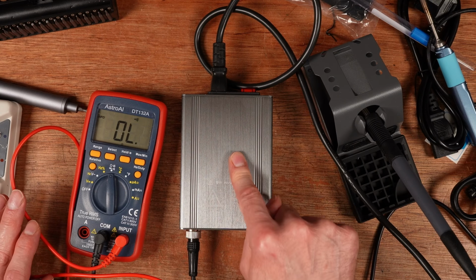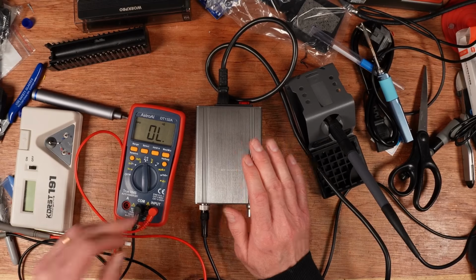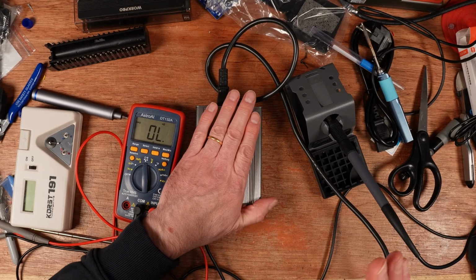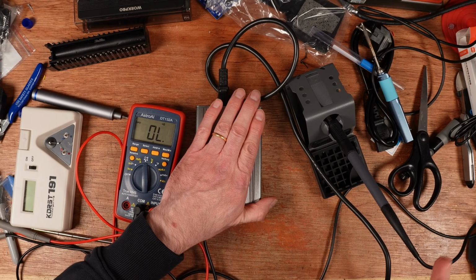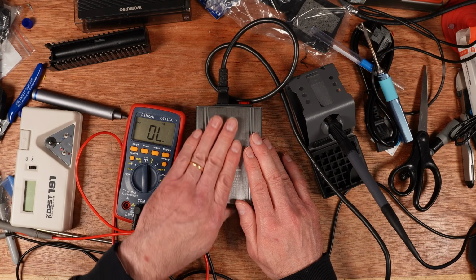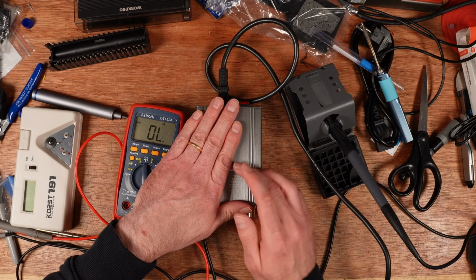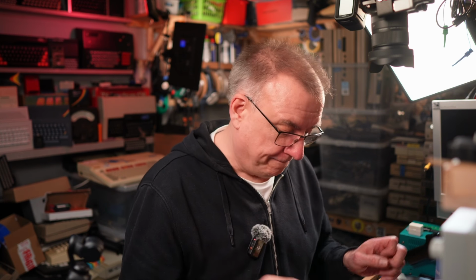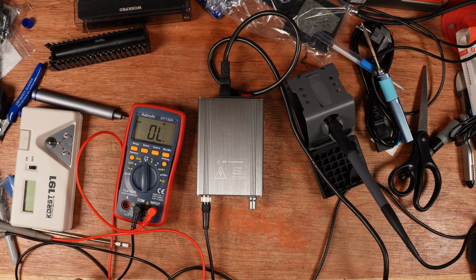If there were 240 volts going through this, and I touch this and say an earthed appliance at the same time, that current would jump that gap. There's not enough clearance between there. That would definitely arc into my hand, go through my chest, and then find its way to earth at the same time, stopping my heart. Yeah, wouldn't be ideal. So that's definitely, not to labour the point too much, a massive problem with this.